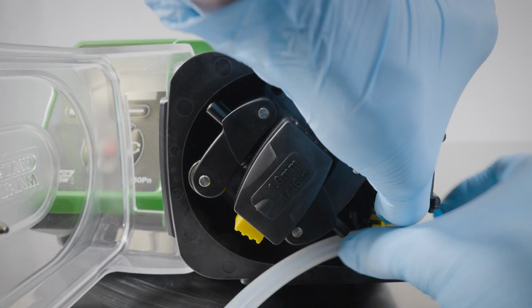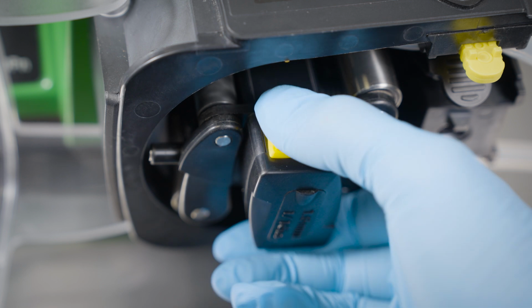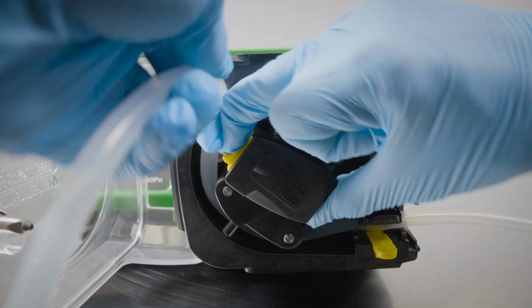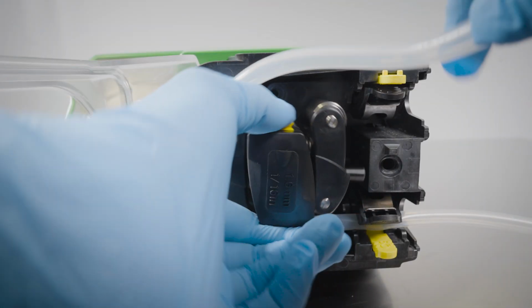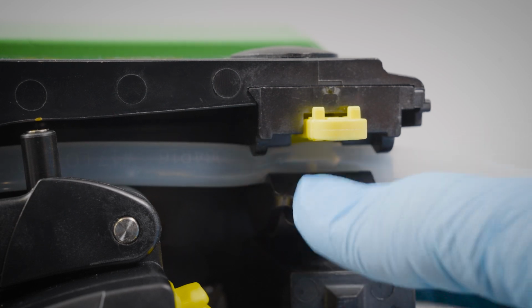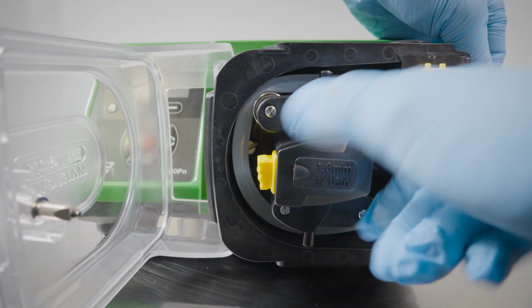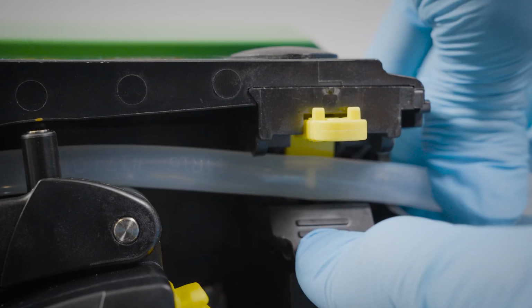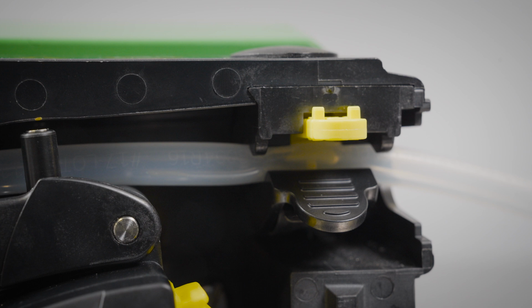Starting at the bottom, push the tube into the clamp. Press and hold the clutch on the rotor. Rotate the rotor assembly as you feed the tubing into the track. Push the tube into the top clamp. Rotate the rotor assembly and then reopen the top clamp to allow excess length of the tube to pass through and for the tube to settle into the track.